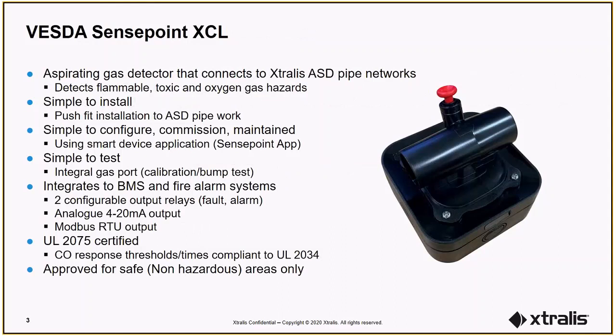VESDA Sensepoint XCL is an aspirated gas detector that connects to Xtralis ASD pipe networks for the detection of flammable, toxic, and oxygen gas hazards. It is inserted inline to the pipe through push-fit connections and is configured, commissioned, and maintained from an app on your smart device. It comes with an integral gas port for in-situ calibration and bump testing without the need to remove the detector from the pipe network.